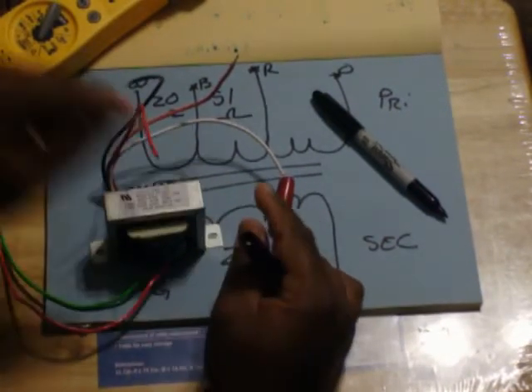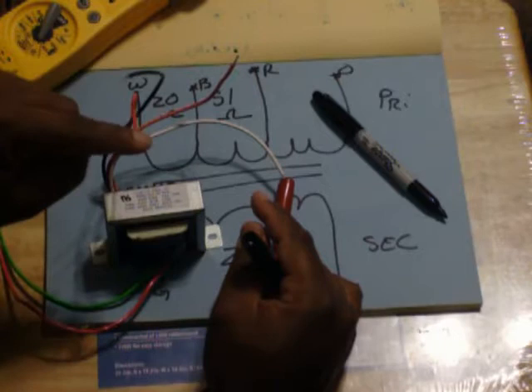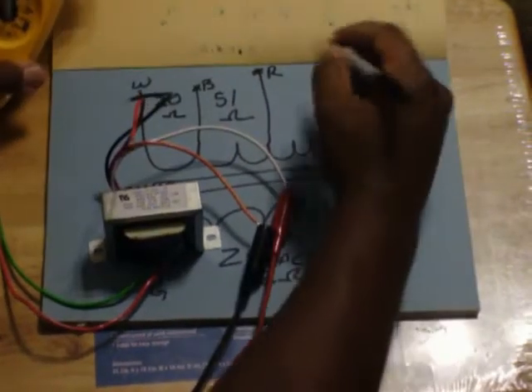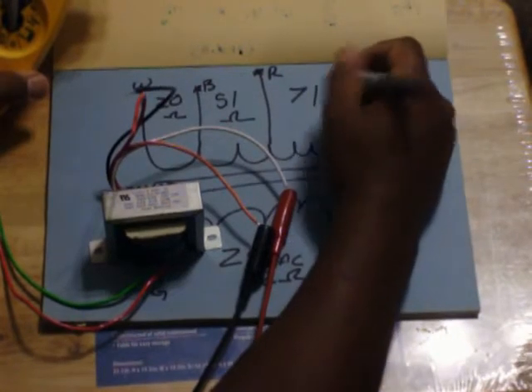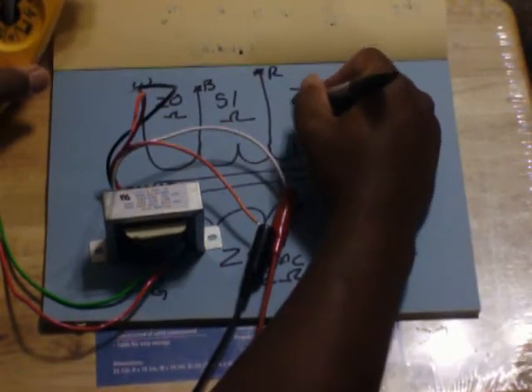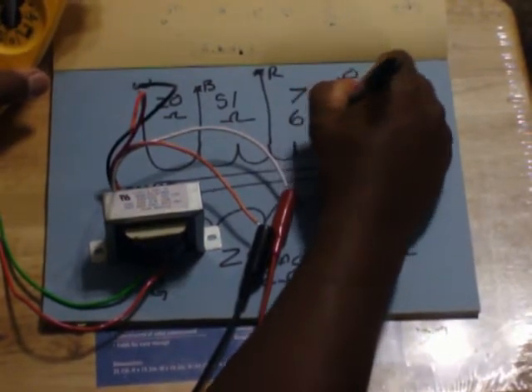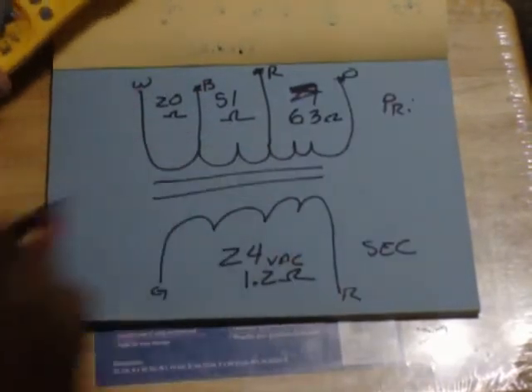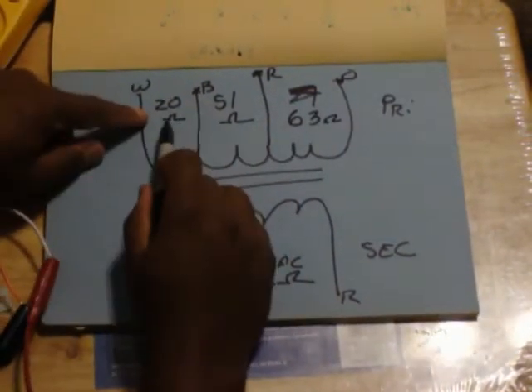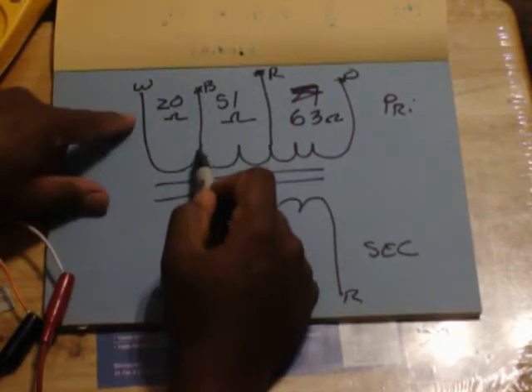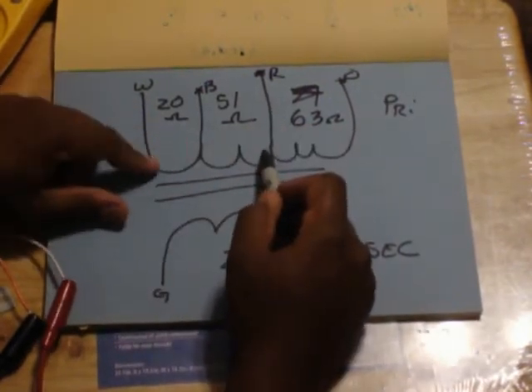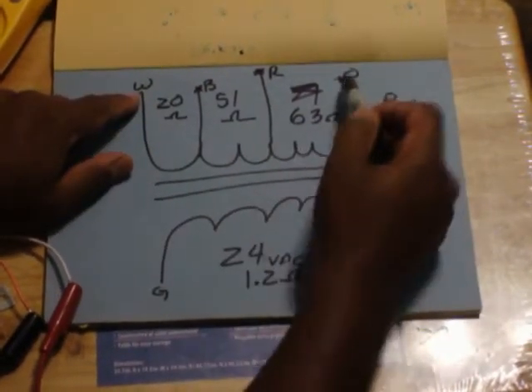Then I'm going to leave it on white again, come off of red. Black was 110, this was 208. Here's 230. 71 ohms. Well, it jumped down on me, I apologize. 63 ohms. So you can see between white and black was only 20 ohms. This little section right here. Then white and red, we went up 30 more ohms. Then white to orange, we went up another 12 ohms.